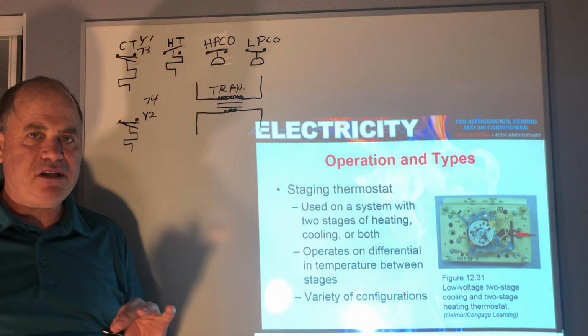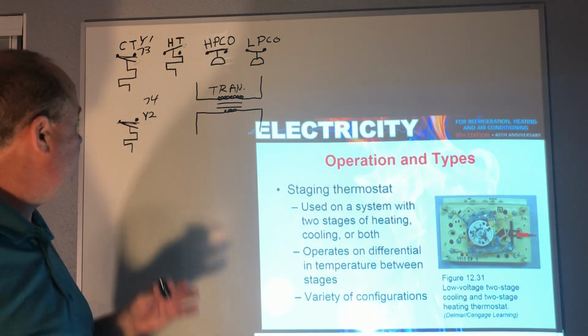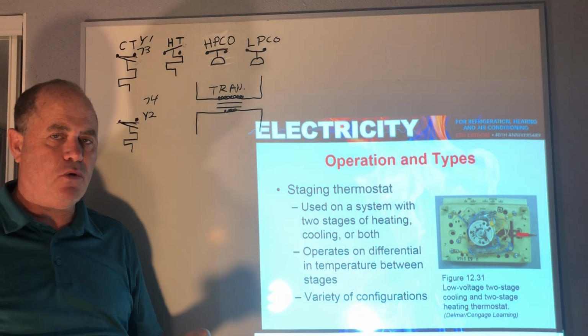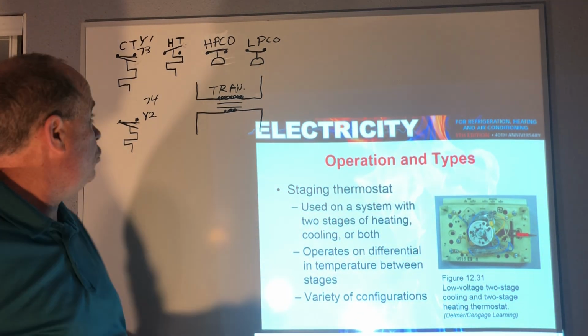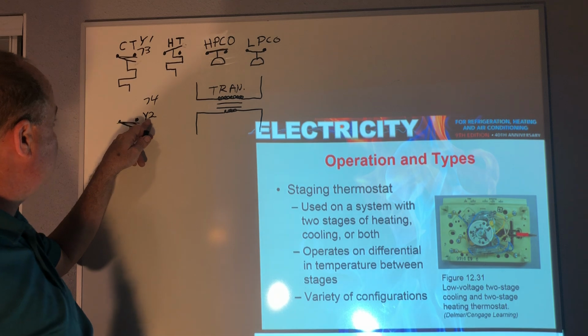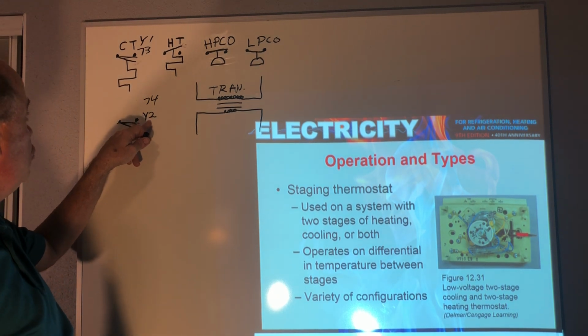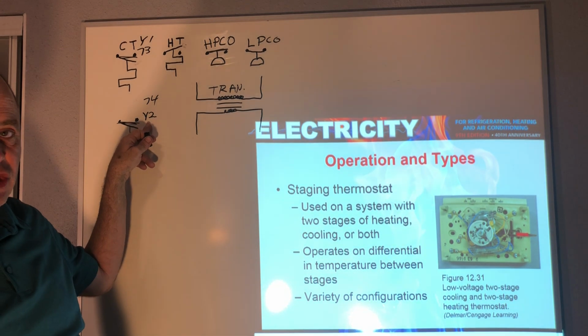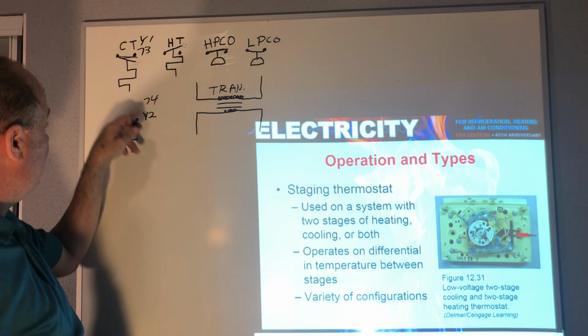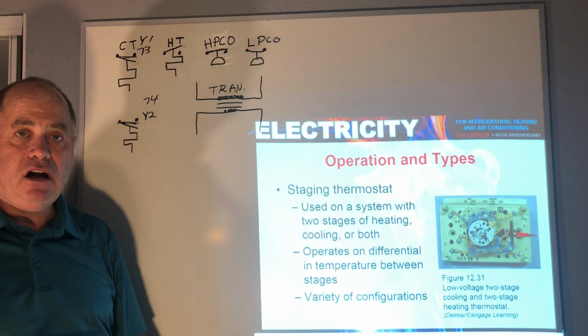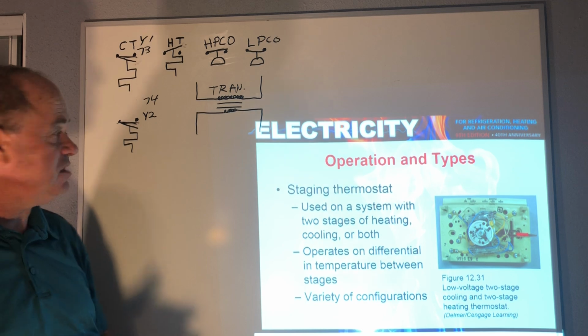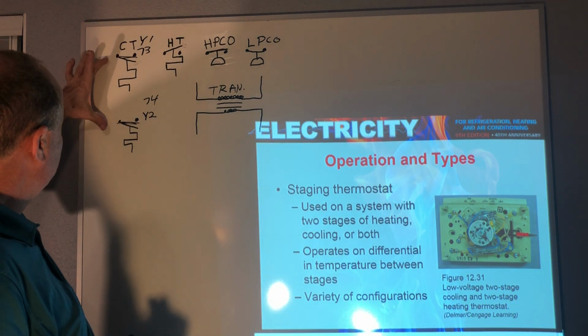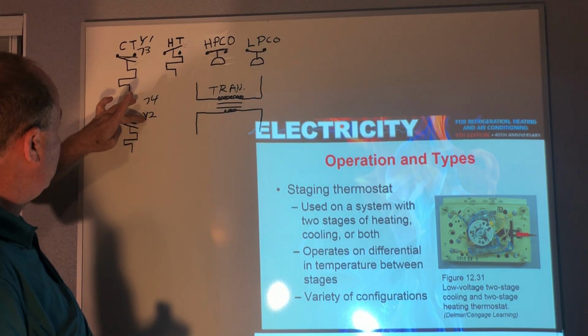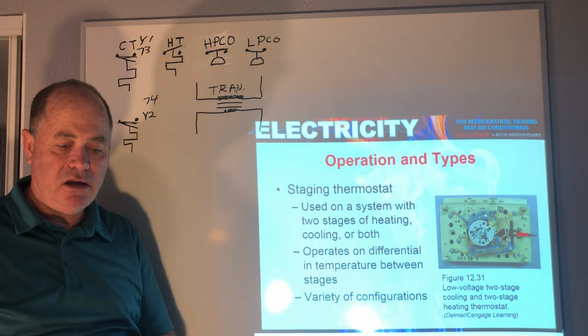So if you're a couple degrees above the set point, you get full cooling. If maybe you're only 1 degree above that set point, you might just get half or 2/3 of the cooling. And then this is the Y2 terminal, or the second stage. So you have this even on some more advanced residential systems. And you can look for this 2-stage with the Y1 and the Y2 on your thermostats.